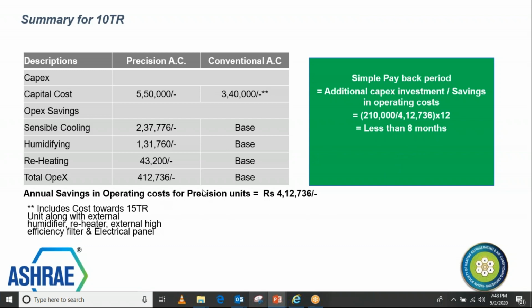Another important aspect which we have not added here in the comparison is the lifespan of the unit. The precision AC life is typically 10 to 12 years, although we see in the industry many units which are running for about 15 years, or even 13, 14 years. So imagine your comfort air conditioning system, if it has to work for 24 hours, 365 days, for 3 years, what happens? If you go to applications which are running 24 hours and you see the situation of a package unit, its cabinet doors are also coming out, the electrical panel, everything, and all components are failing frequently.